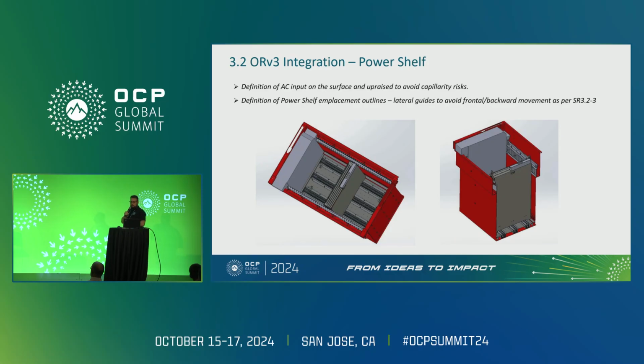This is also the integration board for the power shelf. You can see the power shelf has the AC to DC connector up on the surface, not in the bottom as most power shelves have. This is one of the major changes needed for immersion, avoiding capillarity and other risks. In an immersion tank, having power cables or any cables at the bottom isn't very practical to operate. So we try to keep all connectivity, power, fiber, network copper, on the surface of the tank. The power shelves also have their connectivity on the surface, and we have placement outlines and lateral guides so they can't move left to right, always following a straight direction as we insert them from top to bottom.